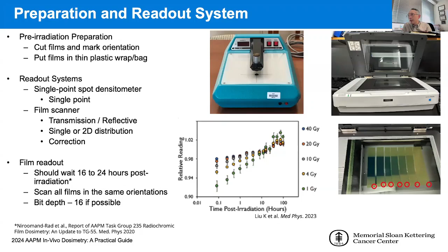And as you can see here, we typically will put a mark when we cut up the film, and when we scan them, we orient them the same way to reduce the polarizing uncertainty. And the last thing is the bit depth. We will recommend 16 bits if possible. For older scanners, it could be 12 or 8 to 12 bits. But if you can, having a deeper bit depth in terms of color resolution would be very helpful.